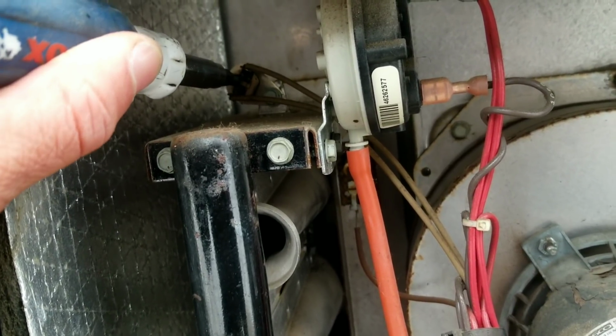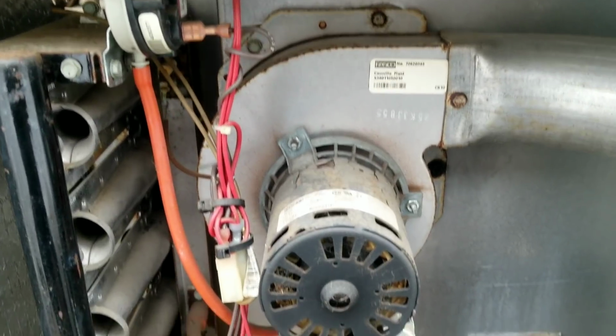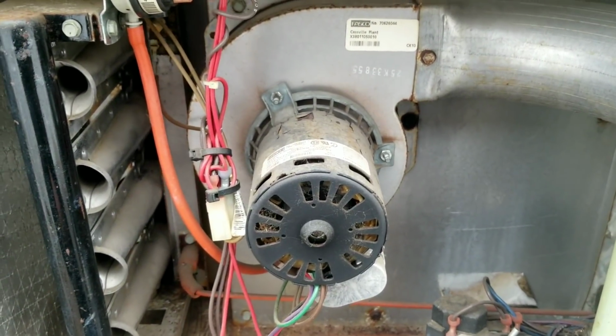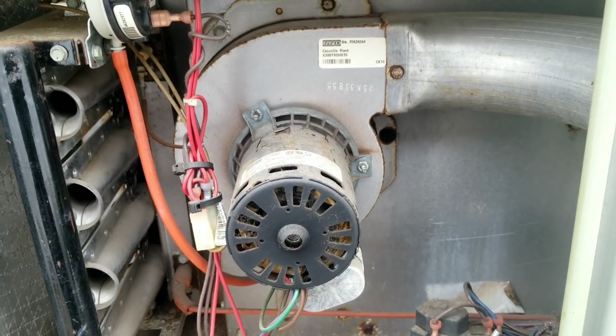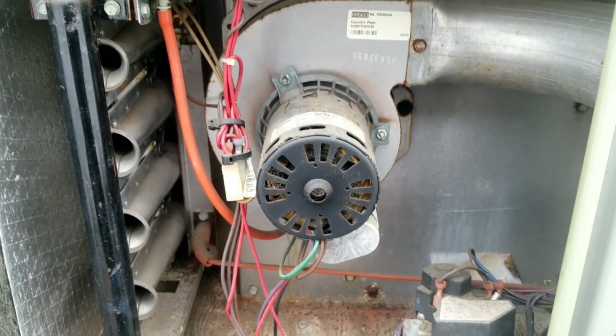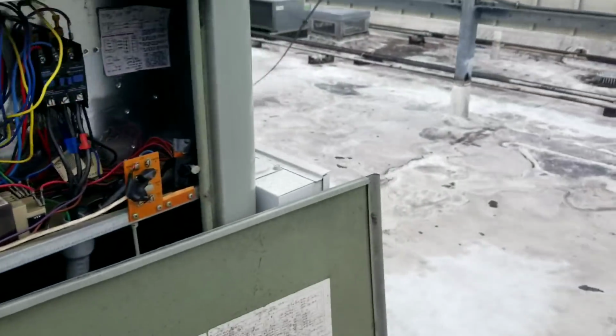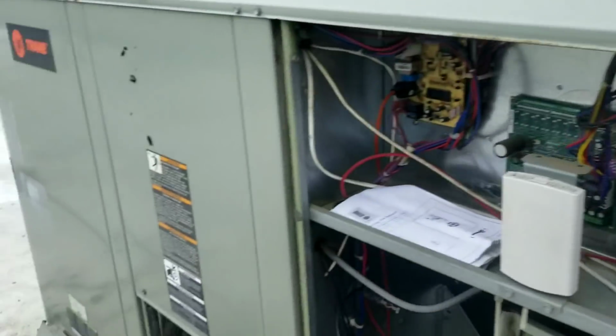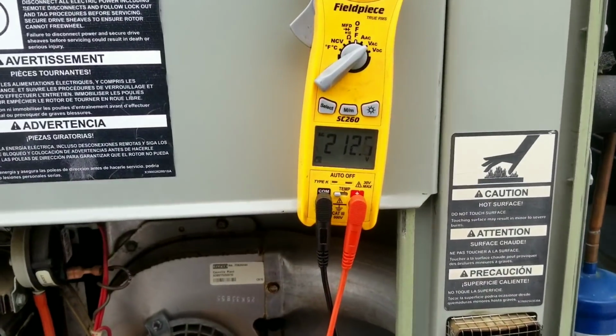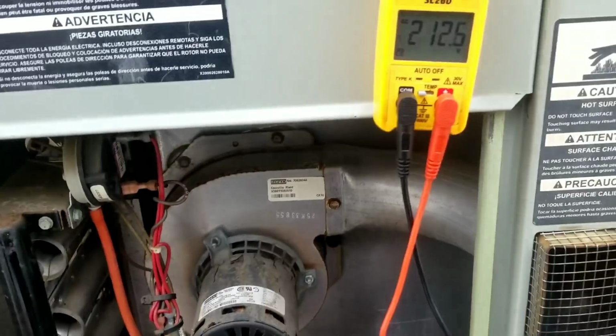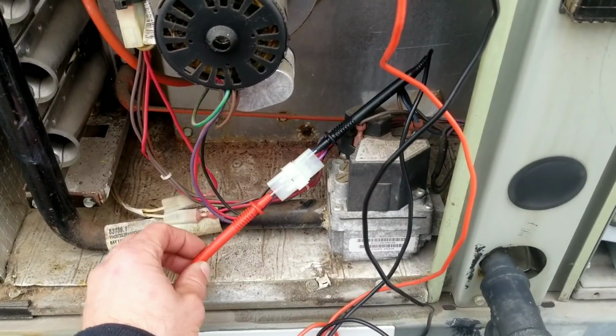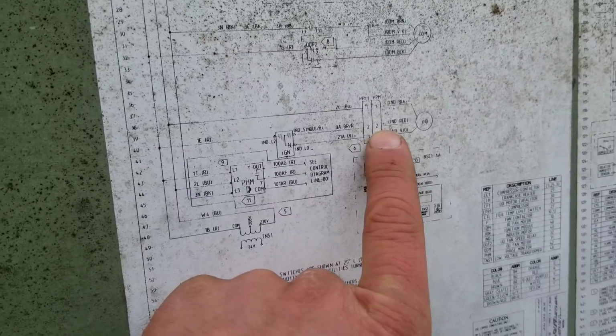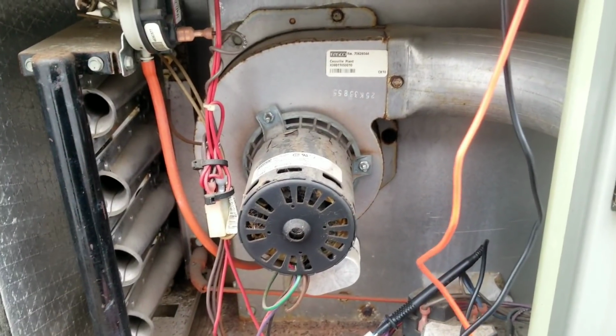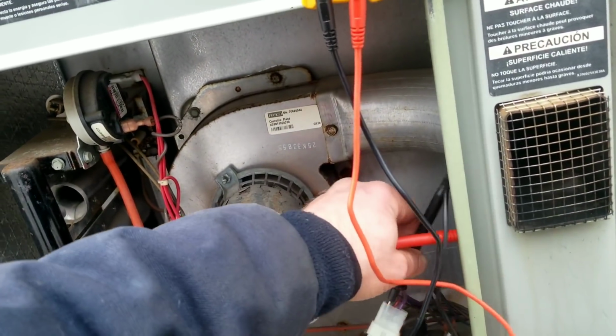You should probably do this. Well, that's dead. Let's power that off instead of just staring at it. Alright guys, there's our noisy inducer motor. I do have 212 volts going to it in my blue and my red, which is my black and my red. We'll double check over here. So high fire. There we go. Anyway, we got voltage to it. It's not turning. We need a new one.